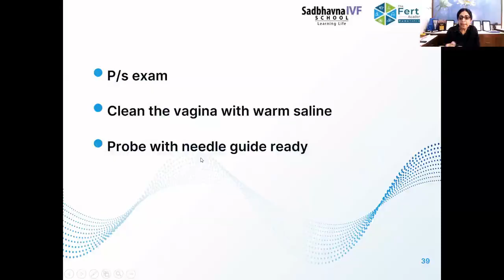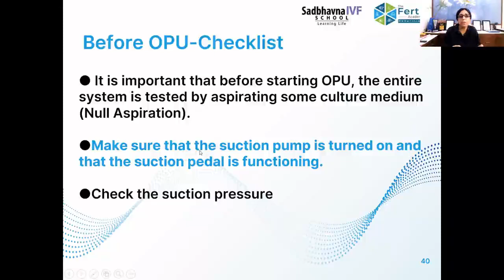Before the OPU checklist: once you've cleaned up everything and your transvaginal probe is in place with the needle guide, you must check by doing some null aspiration to see that there is no crack. At times the round test tube could be cracked, or the needle could be blocked. Just be sure that everything is working before going into the follicle. Check the suction pump and the pressure, whatever pressure you have in mind. We keep our pressures at 100 mm. We tell the anesthetists to keep looking at the suction pressure pump in between so that the pressure does not fluctuate.